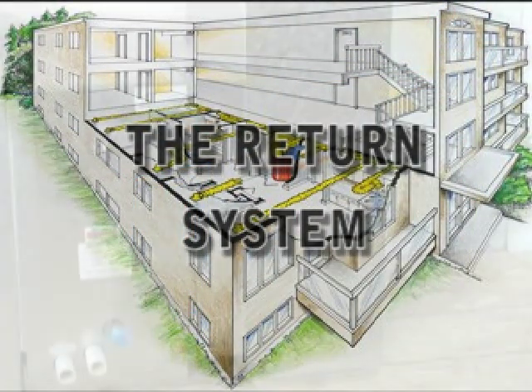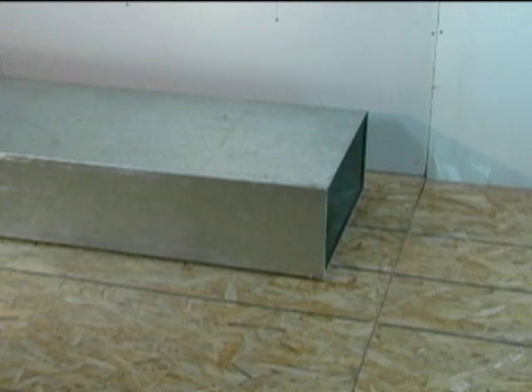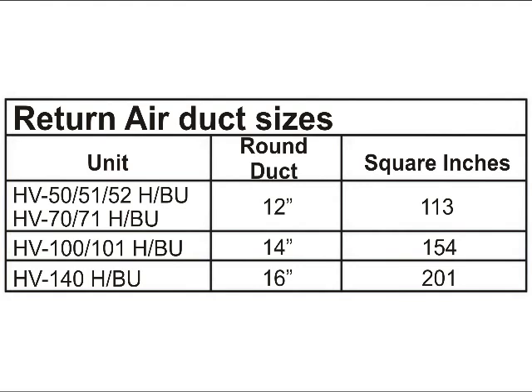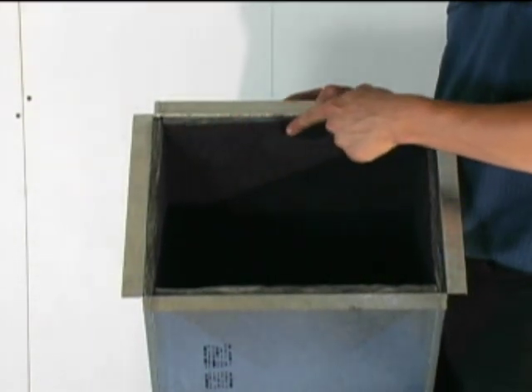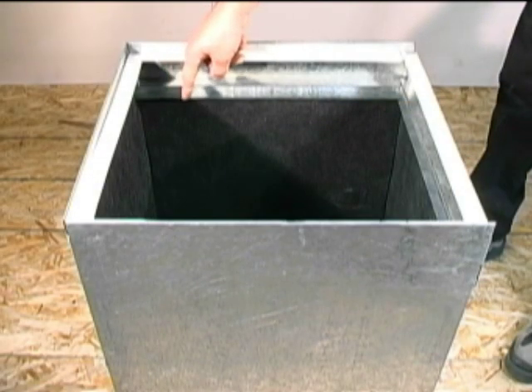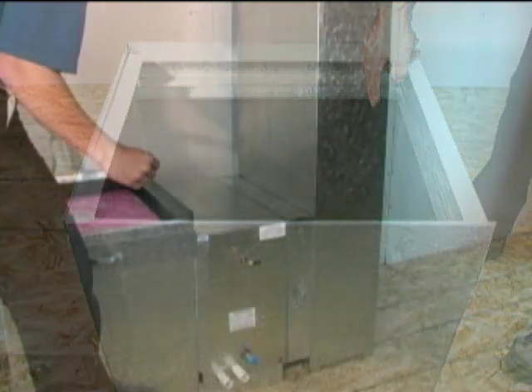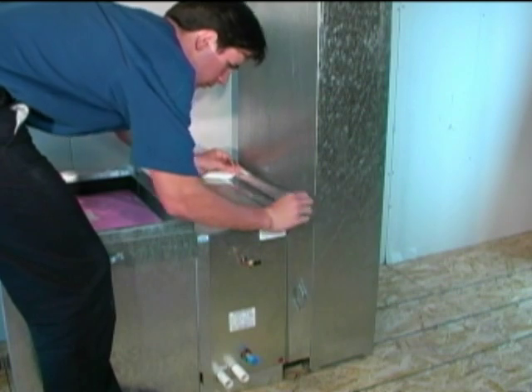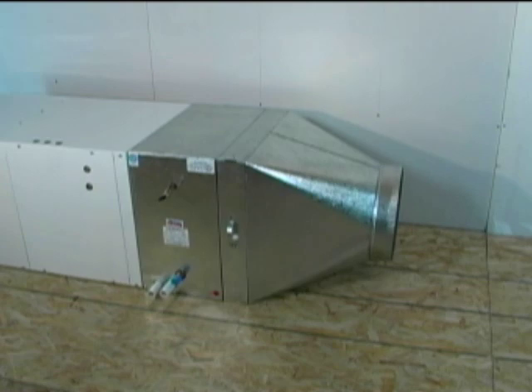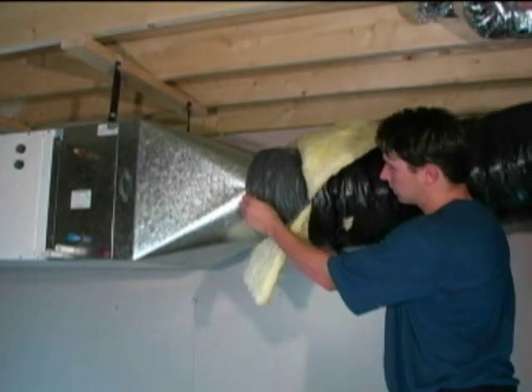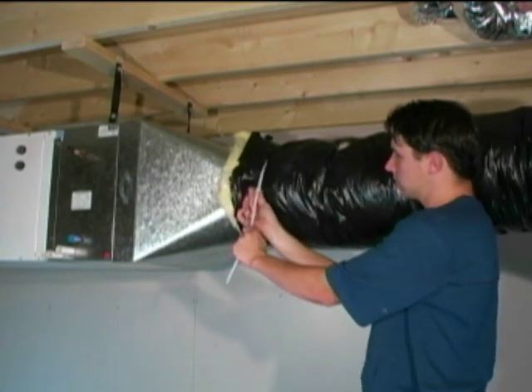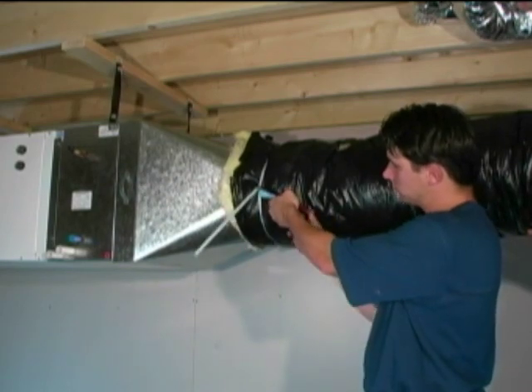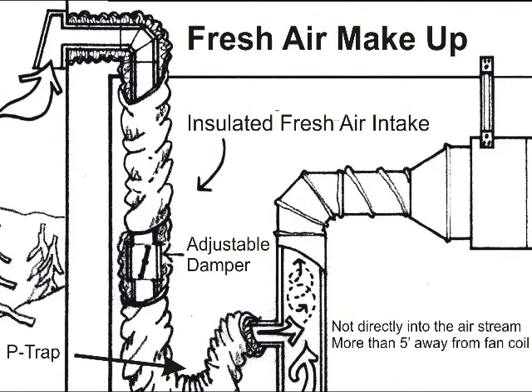The return system. The complete return air system is not supplied by the factory and should be installed according to building codes for your area. Rigid or flexible duct is acceptable with the high-velocity system. Refer to the installation guide for return air sizing. If rigid duct is used, to ensure quiet operation, we recommend the first five feet from the fan coil be acoustically lined. The high-velocity return air base comes from the factory with sound absorbing material pre-installed. With a rigid return air duct, use an approved sealant on all the joining connections to create an airtight seal. When a round flexible return air duct is used, a tapering transition will need to be installed. Secure the inner core of the duct with an approved sealant, then use a cable tie on the outer insulation sleeve. Remember to upsize the return air one size when using flexible duct for the return. Also see the installation guide for tips on installing a fresh air makeup system.